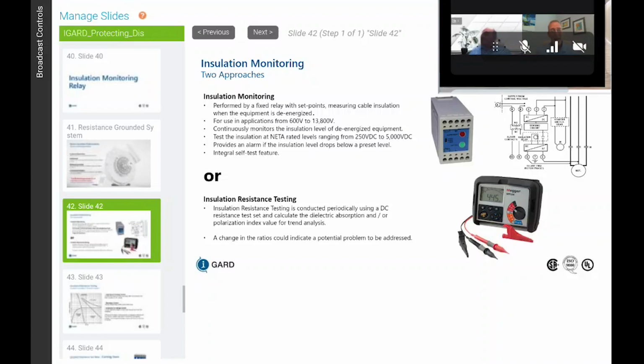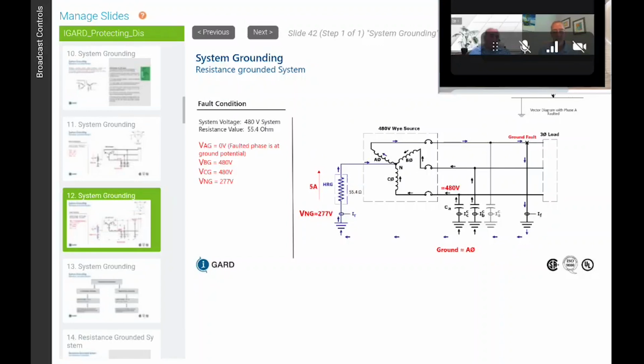Jacob wants to know, since there are many benefits of a resistance grounded system, are there reasons or instances when you wouldn't want to use a resistive grounded system? I think you pointed it out earlier, maybe, but it might be worth reviewing. Yes. One of the disadvantages in using the resistance grounded system is that you do not have phase to neutral loads. So if you have a system, a shopping center, shall we say, and all the lighting is 277 volts, it's not practical to put a resistance grounding system in there.